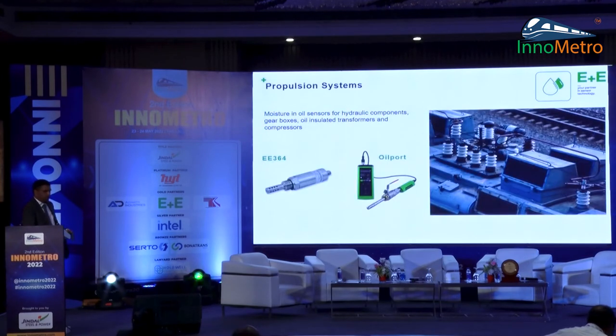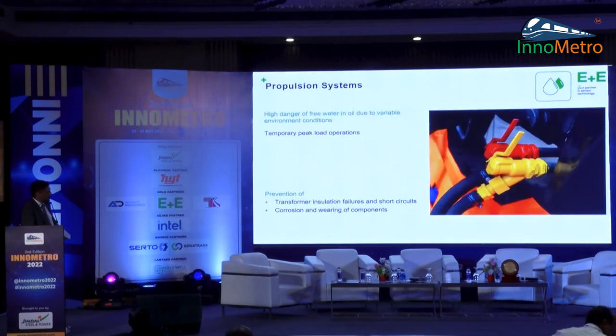The third thing we do is propulsion. Everyone knows how transformer oil plays a pivotal role, and the water in transformer oil reduces the insulation. This is one particular product which we do a lot in India, and it measures the moisture in the transformer oil so that you can do the wear and tear analysis at the right time, maintenance at the right time, and you don't have failures. This is how we prevent transformer insulation failures and short circuits by measuring the moisture in the system.